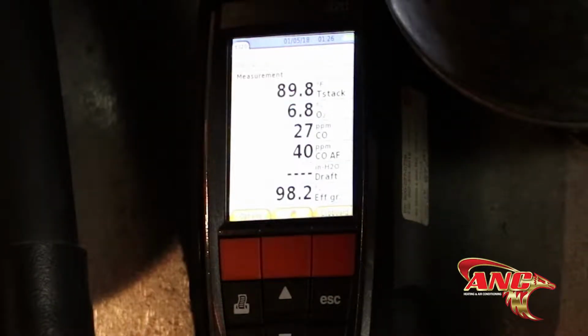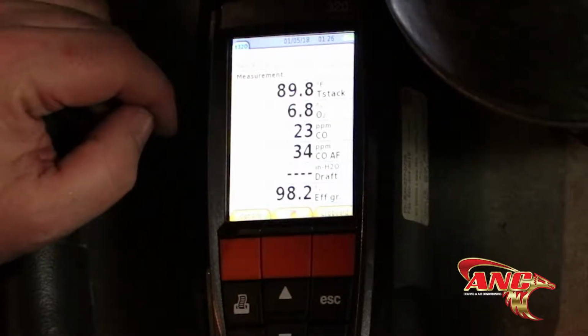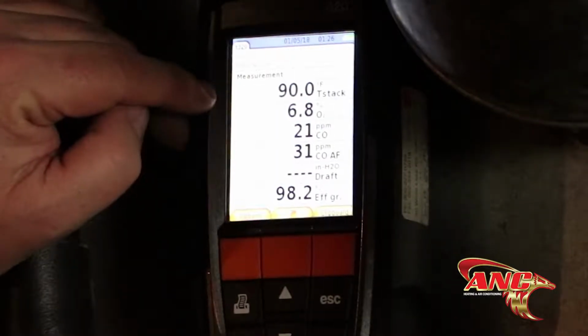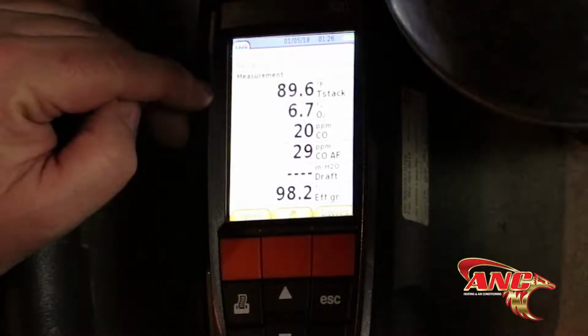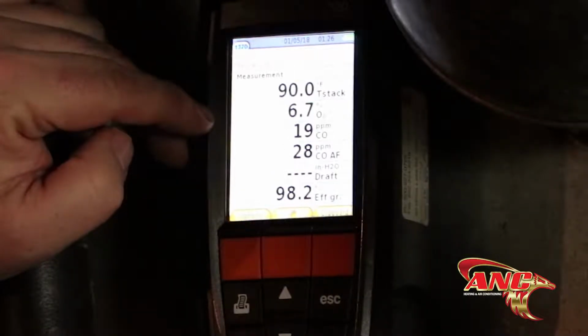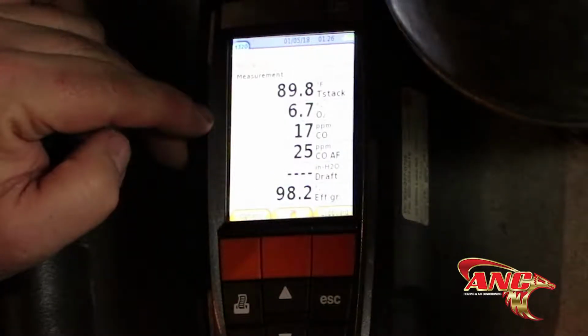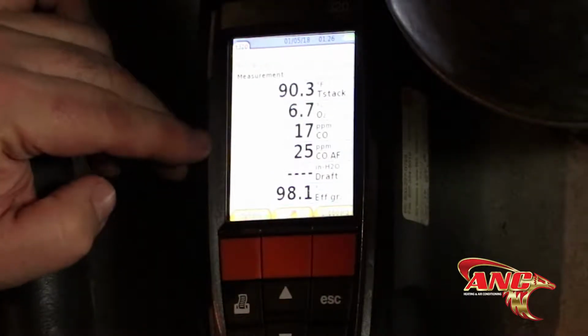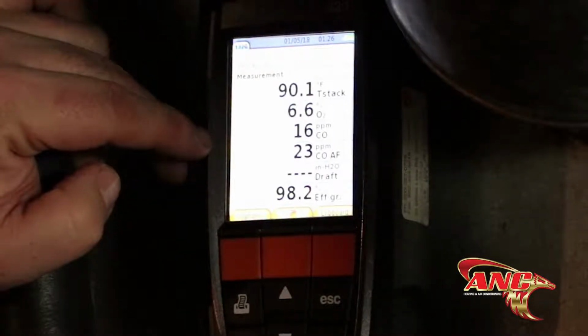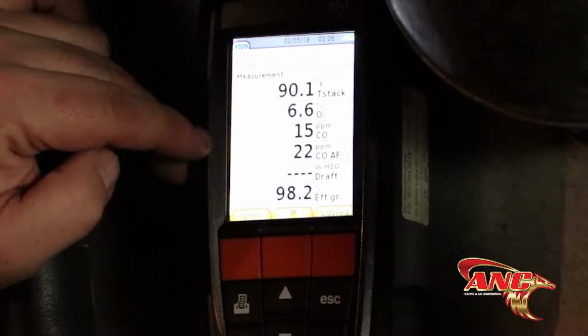So here's a 20, well, math's not my strong point, let's just say a 20-something-year-old unit. It's got a stack temperature of 90, probably going to go up a little bit. Oxygen didn't change, it's right where we want to see it. Carbon monoxide, it's just like a brand new furnace.